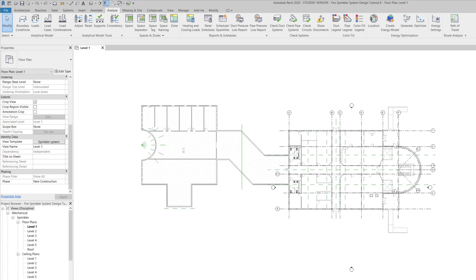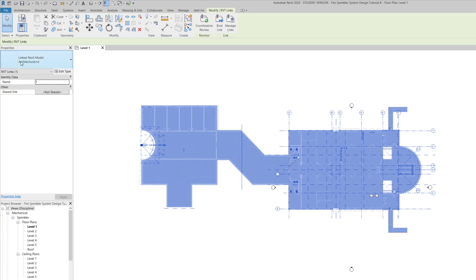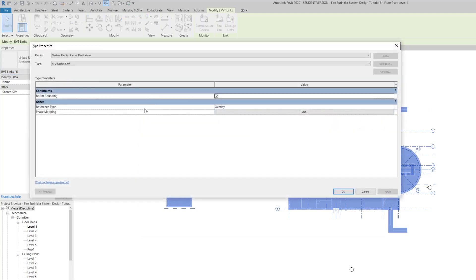As you remember from the Revit MEP HVAC basic tutorial, we determined that the architectural floor plan has its own room names and when we start a project we have the room boundary determined. When you highlight on your architectural background layout and you have the linked Revit model, the architectural model shows up in the properties section on the left side. Once you go to Edit Type, the recommendation from the beginning was to have the Room Bounding option activated, so that every space on your floor plan is determined based on the boundary of the surrounding rooms.